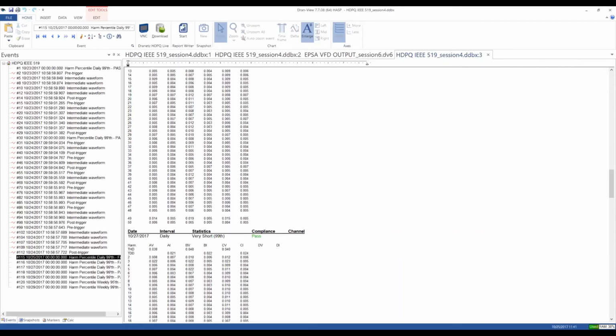So Seth Kumar says that 519-2014 informs daily 3-second and weekly 10-minute intervals and measurements, and goes through a summary of the samples and asks, how do we evaluate that? The way the instrument does it is that it maintains all the statistical data within the instrument itself. And as I mentioned before, the instrument reports based upon the requirements of 519-2014. It does not record all those details to the database. In other words, all the 3-second data, it doesn't record that.